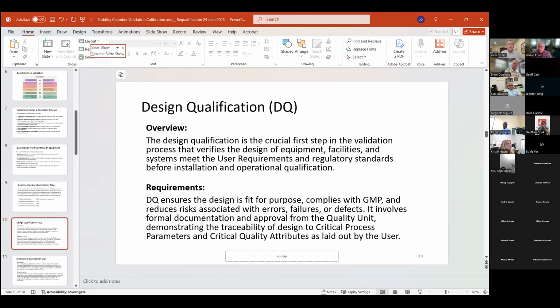With regard to that, the design qualification is the crucial first step in the validation process that verifies the design of the equipment, the facilities that they go into, and systems that are going to meet the user requirements and regulatory standards before installation and operational qualification. The DQ ensures the design is fit for purpose and complies with GMP, reduces risk associated with errors, failures, or defects. It involves the formal documentation and approval from the quality unit, demonstrating traceability of design to critical process parameters and critical quality attributes as laid out by the user.